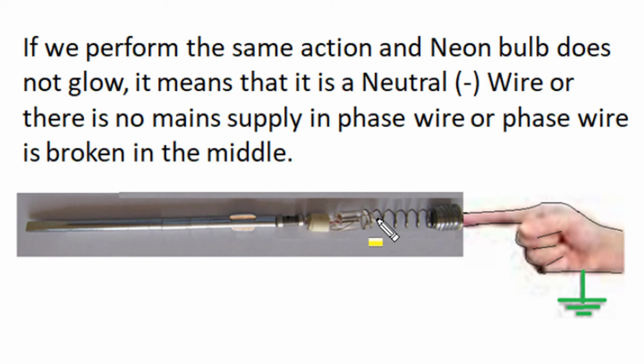If during testing the neon bulb doesn't show any glow, it means there is no current flow. That means the other end of the screwdriver, that is the test probe, and this ground connection have identical potential. It means the test probe is in contact with either the neutral wire or an isolated part of the electric circuit where the main line supply of the phase wire is disconnected or broken somewhere in the middle of the circuitry. So we can say a glow indicates that the test probe is in touch with the phase or line contact position, and no glow of the neon lamp indicates that the test probe is either connected to a neutral point or is in connection with an isolated part where the main supply is disconnected.